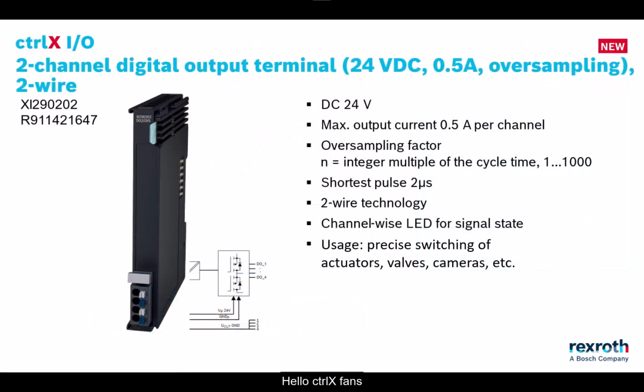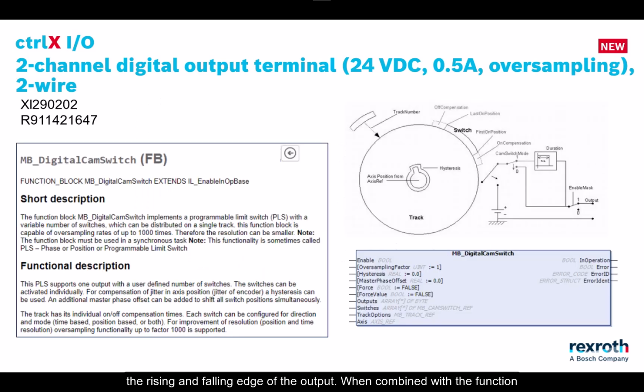Hello ctrlX fans. This is a demonstration of the ctrlX 2-channel Oversampling Digital Output Module. This module divides the EtherCAT cycle into many smaller time slices to enable precise control of the rising and falling edge of the output. When combined with the function block MB Digital Cam Switch, this module provides high-resolution Programmable Limit Switch, or PLS, functionality. It is most commonly used to trigger actuators, dispensers, or cameras at a precise position within the product cycle.